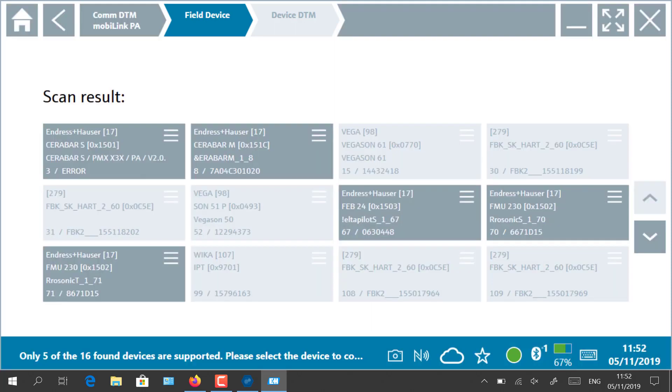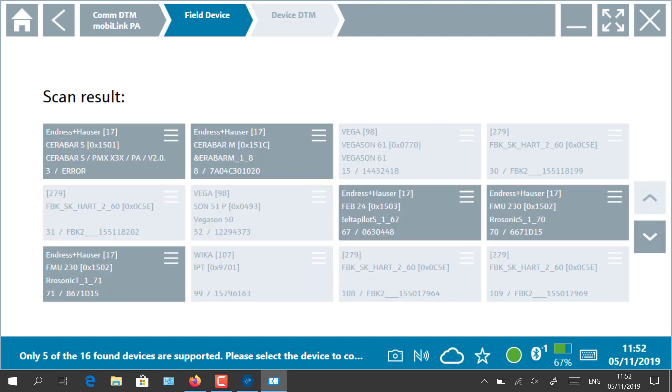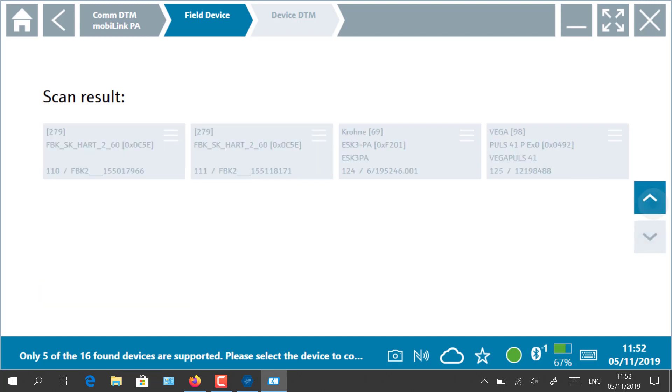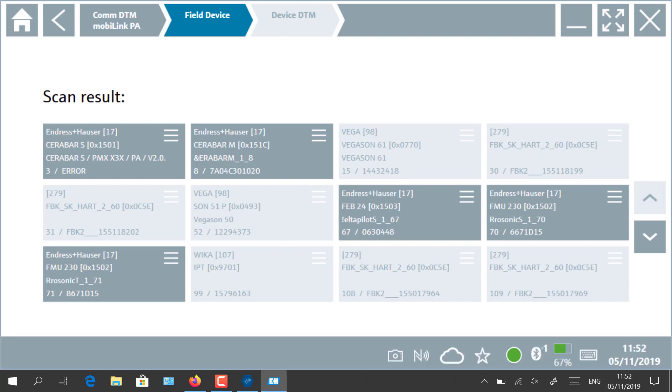All field devices connected to the trunk will be detected and displayed in the tool. Be sure to have installed all device DTMs accordingly. In our case, 16 devices have been discovered. Click on the device and select the vendor-specific DTM for starting the asset management. In our example, we selected the Cerabar M from Endress+Hauser.